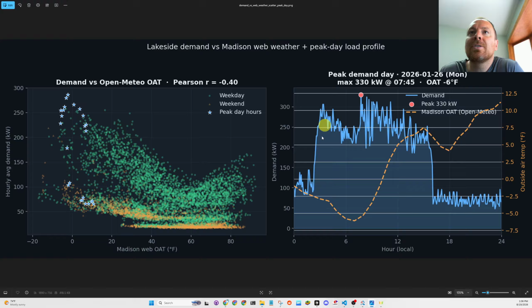And they peaked it right here. You can see the HVAC system started at 3 o'clock in the morning probably, and then it must have gotten up to set point. Kids probably start arriving around here, and then you start ramping up again with plug loads, and who knows what the building's doing then too. HVAC system starts responding, other loads in the building like electrical load, lighting loads, plug loads. There's a dedicated outside air HVAC unit too for ventilation, and that's where they peaked.